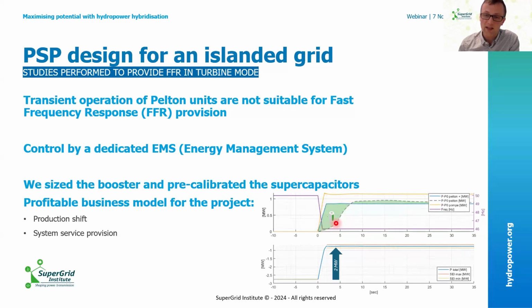You have in black dashed the Pelton response, which obviously is not suitable for fast frequency response. You can see that it's responding much slower, and then it's overshooting besides. And so we compensate with the supercapacitors here in green, and we make the blue response, which is acceptable for the fast frequency response.